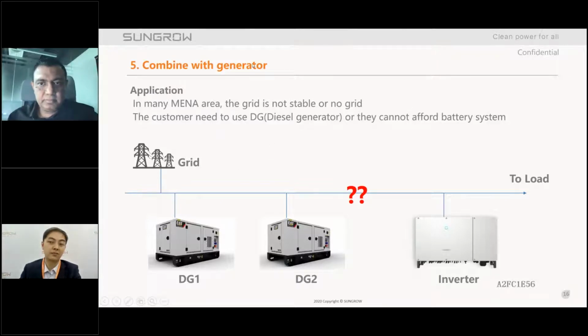In recent years, more and more customers are requiring us to connect the generator with the inverter. Before, the answer was no, because if you connect the inverter with the generator, when the load is not enough, the inverter may generate reverse power to the generator, and this reverse power will damage the generator. So it's very dangerous to connect them together, and we could not do it.